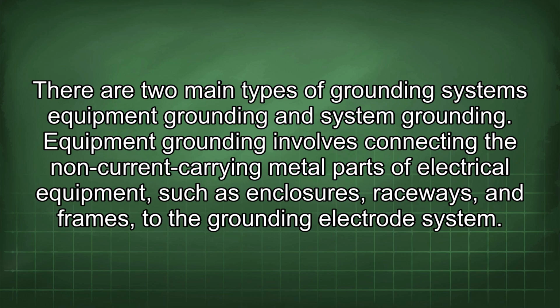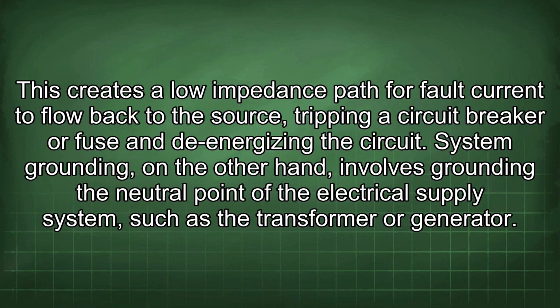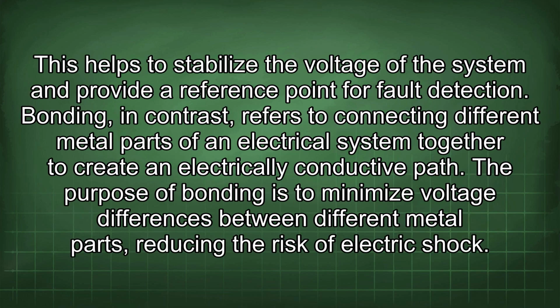Equipment grounding involves connecting the non-current carrying metal parts of electrical equipment, such as enclosures, raceways, and frames, to the grounding electrode system. This creates a low impedance path for fault current to flow back to the source, tripping a circuit breaker or fuse and de-energizing the circuit. System grounding, on the other hand, involves grounding the neutral point of the electrical supply system, such as the transformer or generator. This helps to stabilize the voltage of the system and provide a reference point for fault detection.